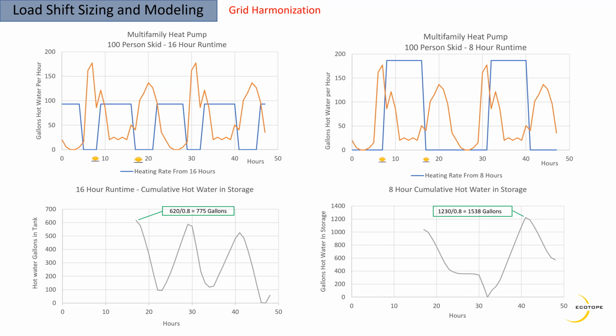In this case, feeding 100 people with the current load I entered on the heat pump, 775 gallons will allow us to shift our load around on a 16-hour runtime. If we look at the 8-hour runtime on the right, this is purely a heat pump set up to only operate during the solar window, 8 a.m. to 4 p.m. The amount of water it has to make is essentially double. If we're taking 16 hours of work and trying to do it in 8 hours, everything doubles. You can see the curve below: we make a lot of hot water during the solar window, then bleed it off until we get down to essentially zero, and then fire it back up. That essentially doubles the storage size, so you can see the impact on your sizing.